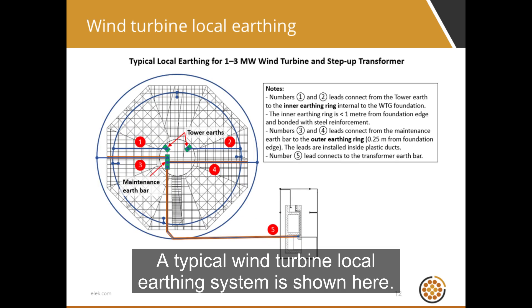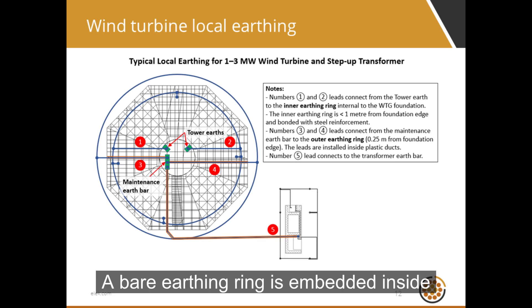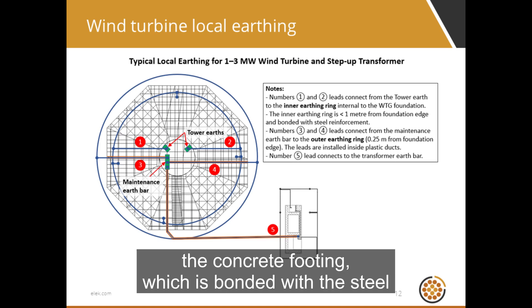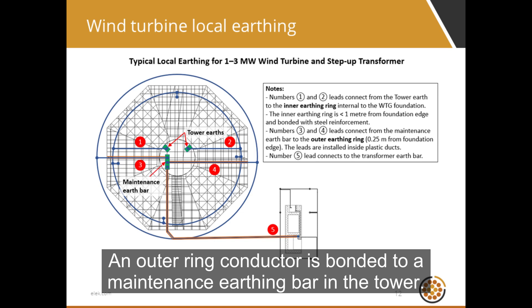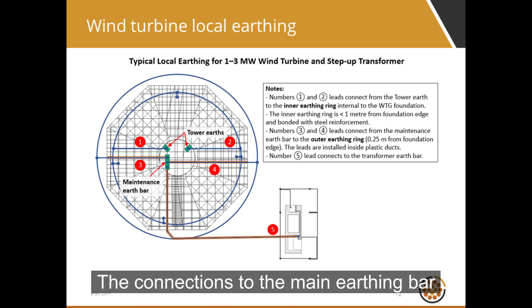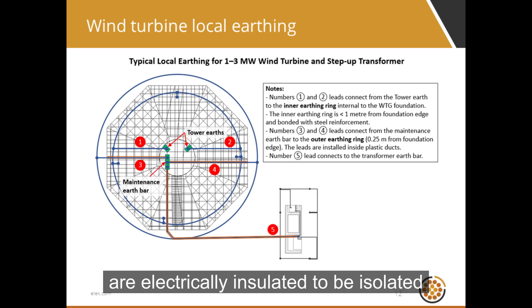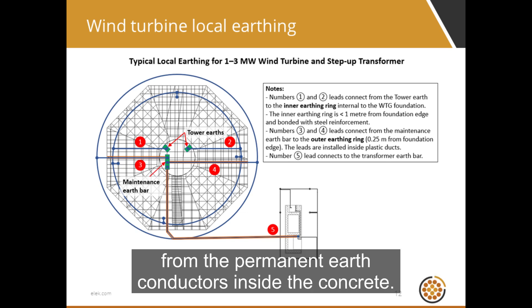A typical wind turbine local earthing system is shown here. A bare earthing ring is embedded inside the concrete footing, bonded with the steel reinforcement and permanently with the tower earthing points. An outer ring conductor is bonded to a maintenance earthing bar in the tower. The connections to the main earthing bar are electrically insulated to be isolated from the permanent earth conductors inside the concrete.